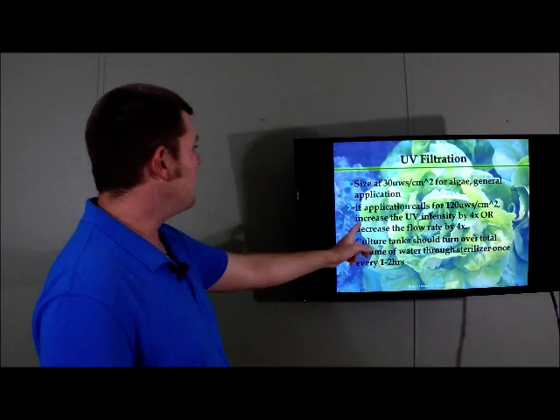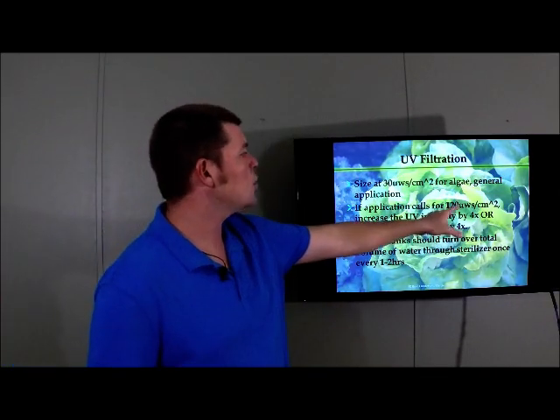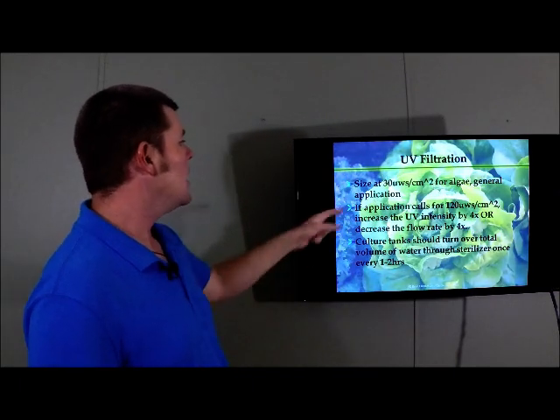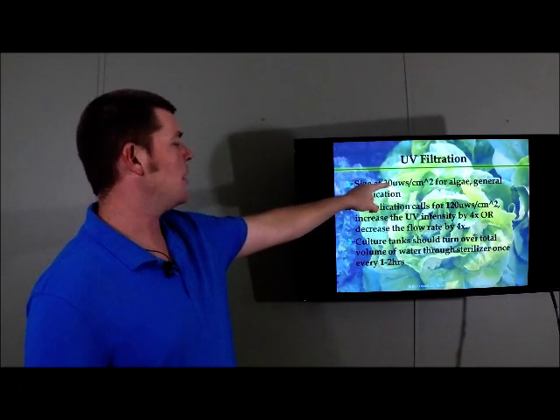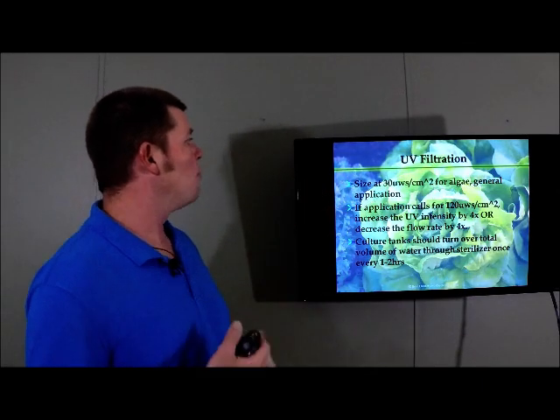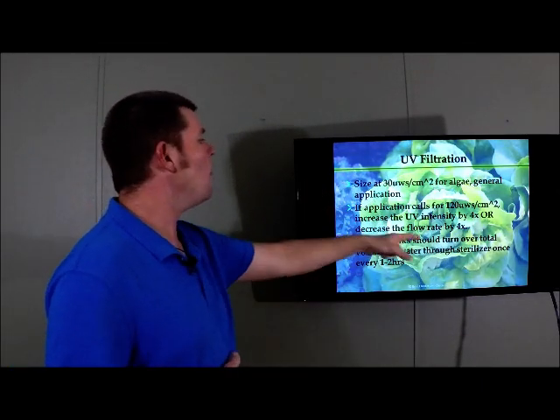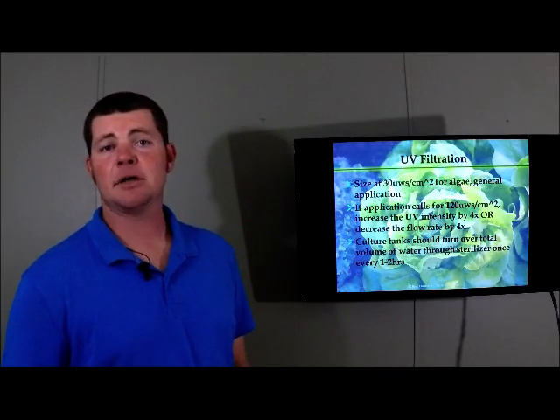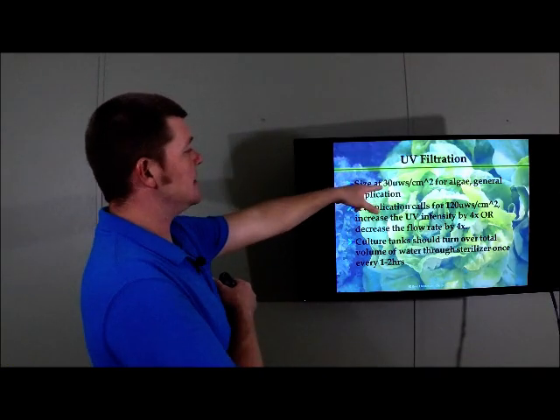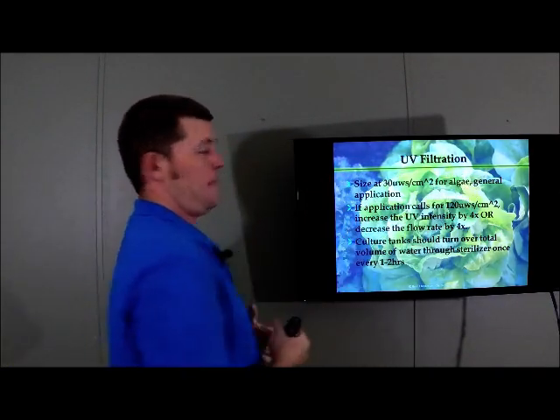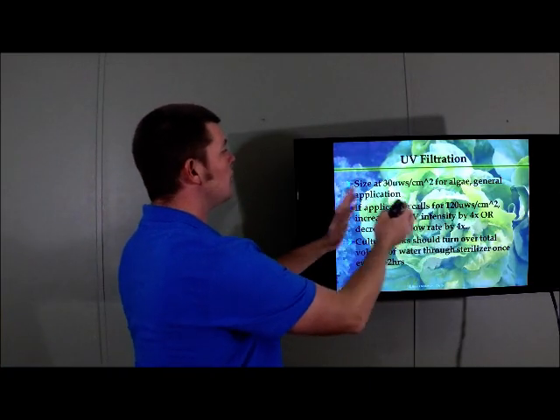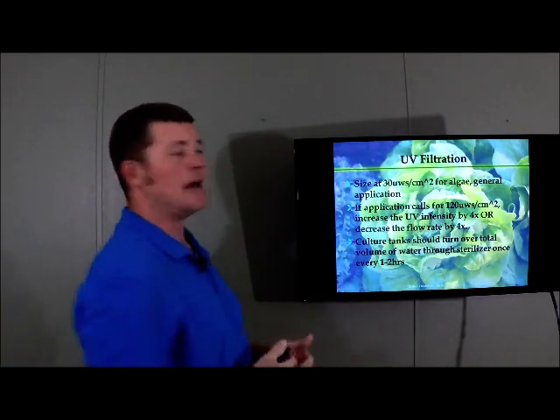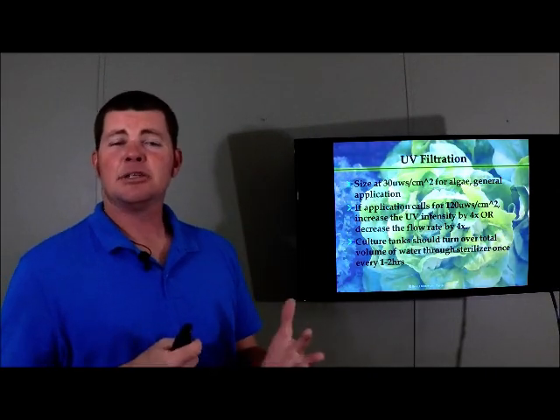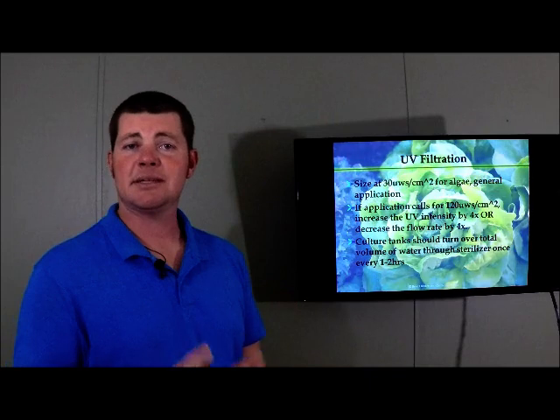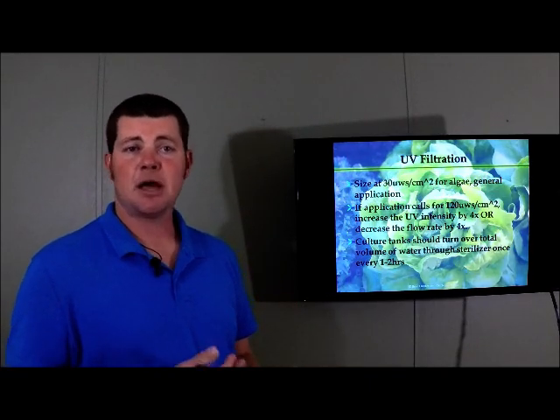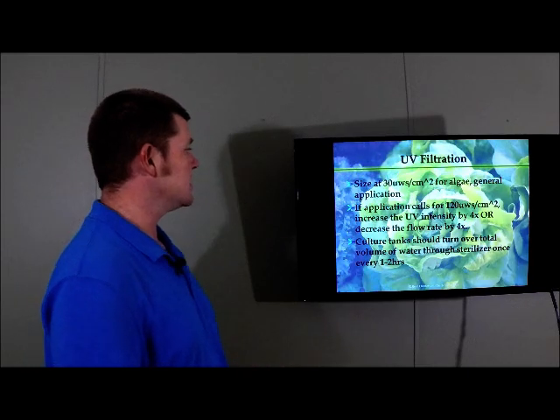That's not the case. If the application calls for 120,000 microwatt seconds per square centimeter, we can increase the UV intensity by 4 from 30,000, getting a light source 4 times more intense, or we can decrease the flow rate by 4 times. If you increase the intensity 4 times, you get that intensity at the given flow rate. If you decrease the flow rate by 4 times, you get 4 times the exposure at 30,000 microwatts, and you still get that intensity. So I hope you see the relationship between intensity, flow rate, and exposure time within these UV filtration systems.